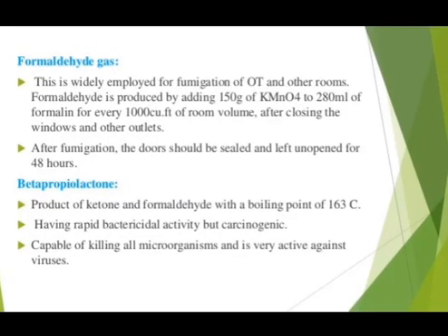Formaldehyde gas is widely employed for the fumigation of the OT and other rooms. This is produced by adding 150 grams of potassium permanganate to 280 ml of formalin for every 1000 cubic feet of room volume after closing the windows and other outlets. After fumigation, the door should be sealed and left unopened for 48 hours.